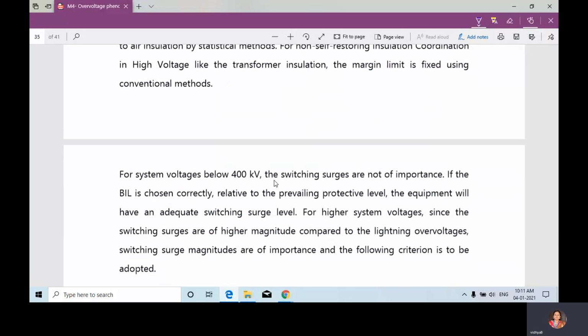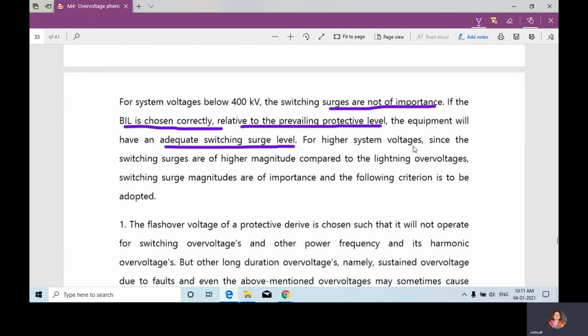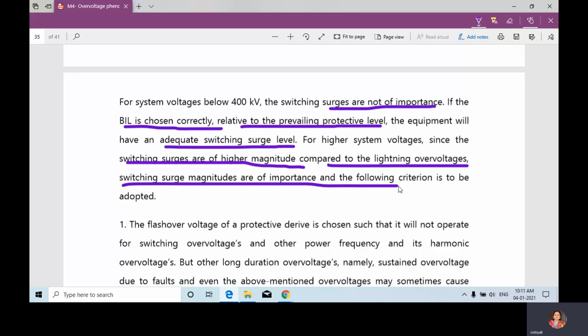For system voltage below 400 kV, the switching surges are not of importance. If the BIL is chosen correctly relative to the prevailing protective level, the equipment will have an adequate switching surge level. For high voltage systems, since the switching surges are of higher magnitude compared to the lightning over voltages, switching surge magnitudes are more important and the following criterion is to be adopted.